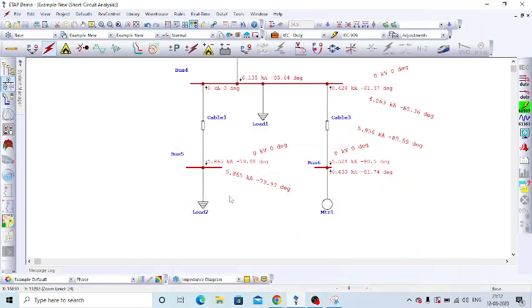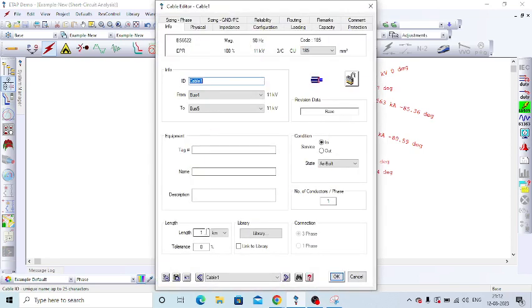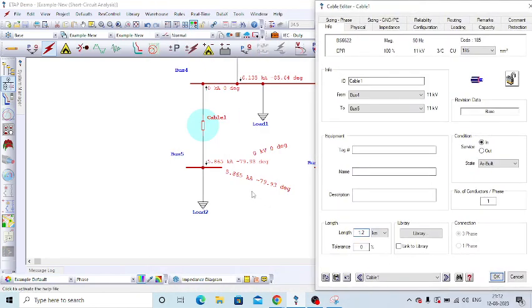So in place of 5 kiloampere, we can go to a higher rating, that is option 1. Suppose that option is not feasible, then alternatively, if the project is in the planning stage, we can add some more impedance in this cable. If the impedance increases, it will definitely reduce some amount of fault current. If the length increases, the cable impedance also increases. So in place of 1 kilometer length, I'm changing it to 1.2 kilometer length. Presently it is 5.865 kiloampere. After changing, it will change.